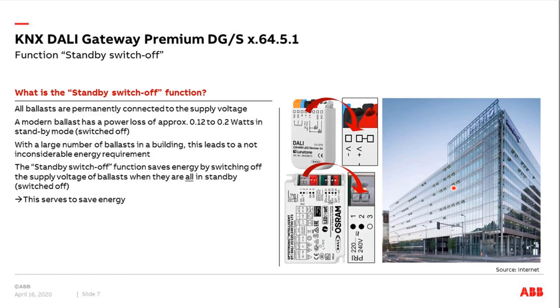In a typical office building we can have more than 10,000, 20,000, or sometimes 30,000 ballasts and more. When you multiply so many thousands of ballasts by the standby power loss of the DALI devices, the total energy waste is significant. With the standby switch-off function, it is possible for the DALI gateway to automatically switch off the supply voltage to the ballasts, saving a lot of energy in the building.